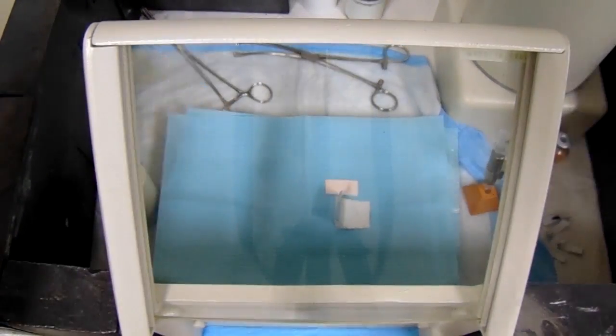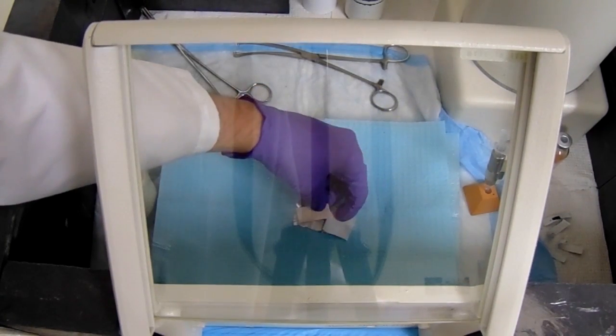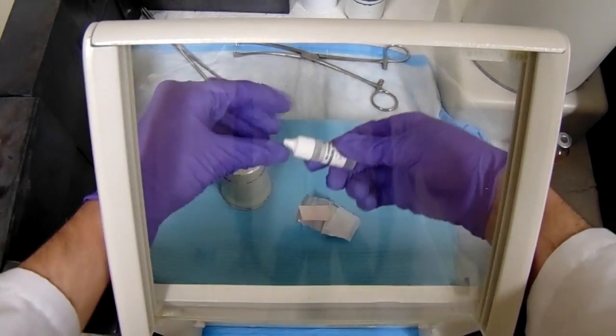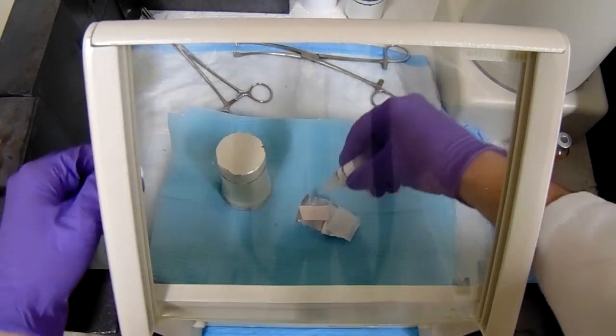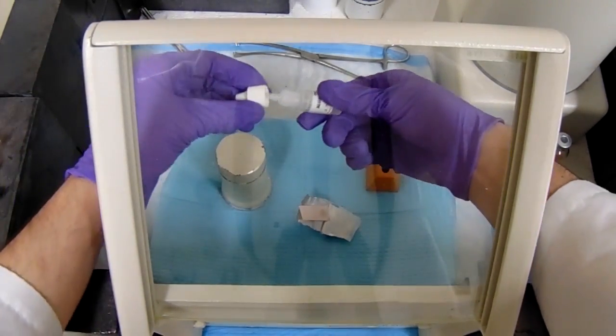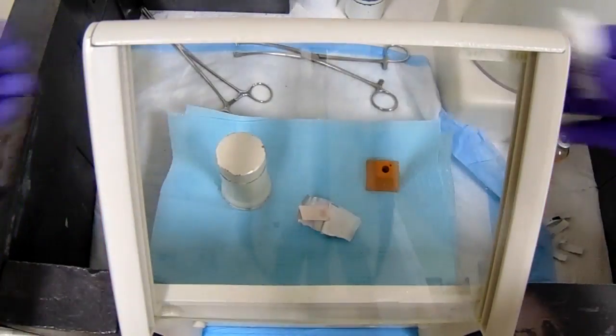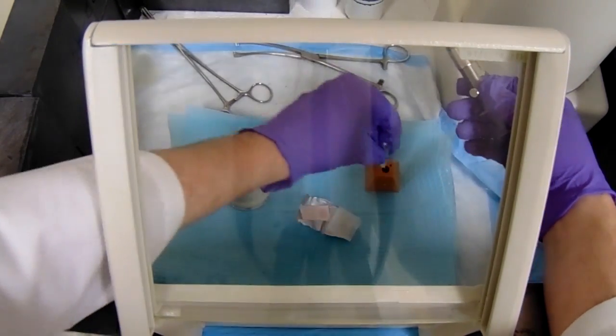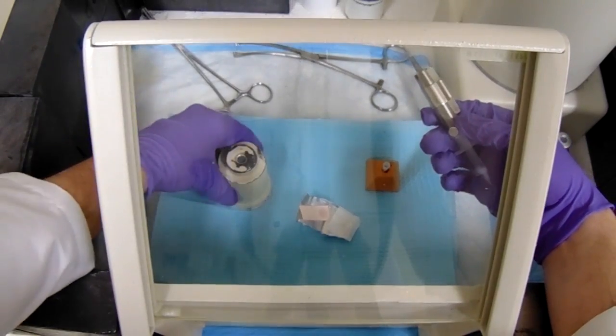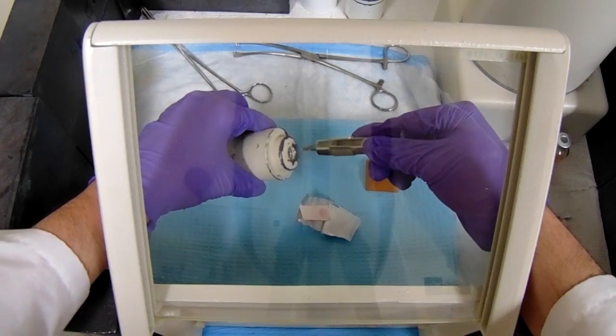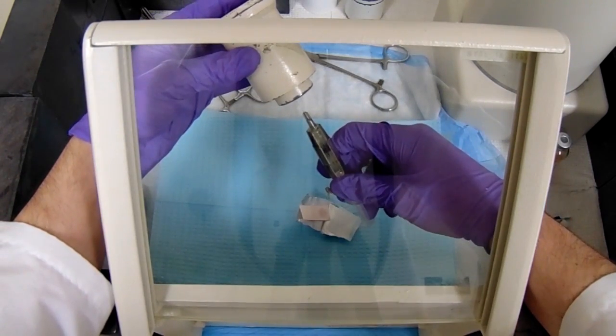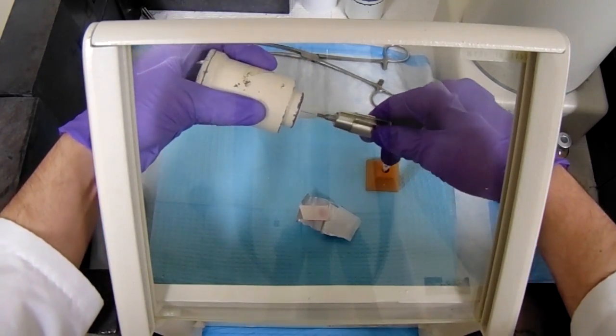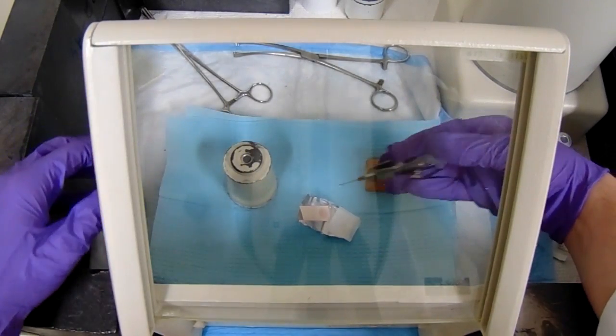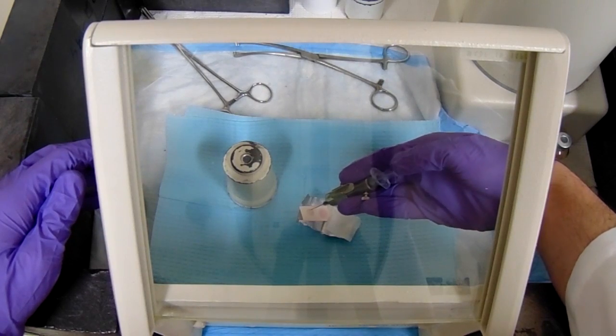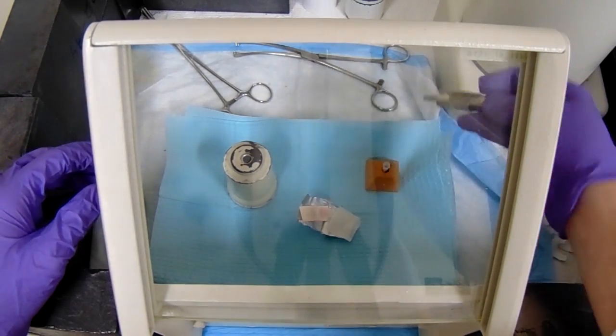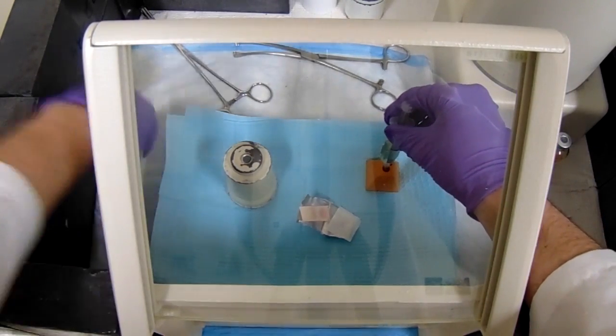Then you're going to need a syringe with a syringe shield and a nerd or a needle recapper. Now you're going to take the bottle of alumina solution and put one drop on one side of the test strip. Now you don't need this bottle anymore, so it can go back in the case. Now you're going to take your needle and put the cap in the nerd, take the lid off your pig with your elution, and then slide the needle through the septum into the pig, and then draw up a very small amount of radioactivity. You only need a drop to do this test, so there's no point in pulling out a bunch. So now you're going to put one drop onto the other side of the strip, and then put your needle back into the cap and recap your pig.